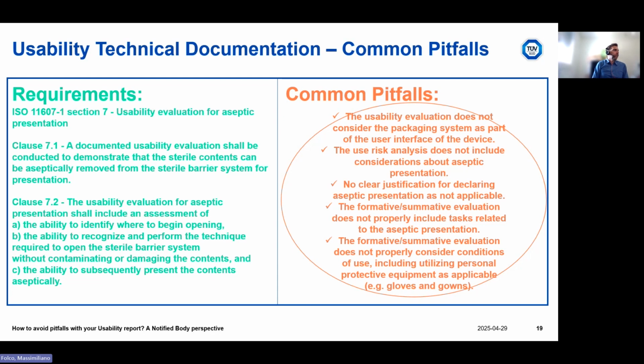Section 7 of ISO 11607 requires performing a documented usability evaluation to demonstrate that the sterile contents can be aseptically removed from the sterile barrier system for presentation. A basic concept behind this request is also the fact that the sterile barrier system, the packaging of the device, is to be considered part of the user interface of the device. So in addition to the device, you have labeling materials, training materials, and also packaging as part of the user interface of the device, for which usability evaluation shall be performed.